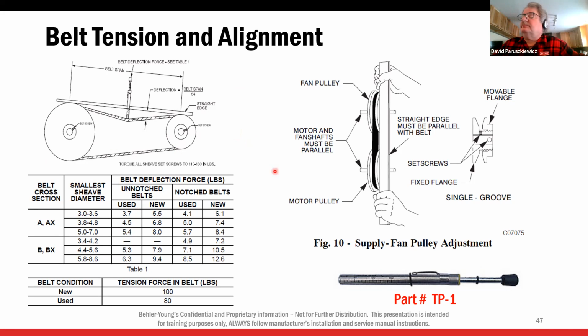This little chart here is out of the installation manual. Now, if you have clean knees, it means you're not reading the installation manuals. Read the manual, or at least the pictures. Wherever there's a picture like this, stop and read it. This is the blower pulley and this is the motor pulley. What they have us do is measure the span between the drive pulley center and the blower pulley center, then measure our smallest sheave diameter, which would be the motor drive pulley. Let's say it's 3.8, let's say it's 4 inches. We're using a brand new notched or cogged belt, so we go over here, notched or cogged belt, new. So 7.4 is the inch pounds of tension on that belt.